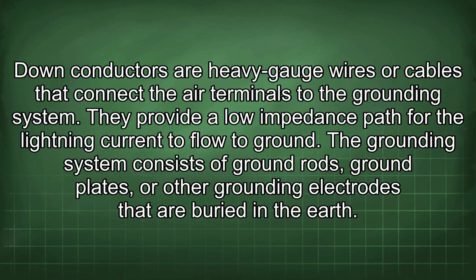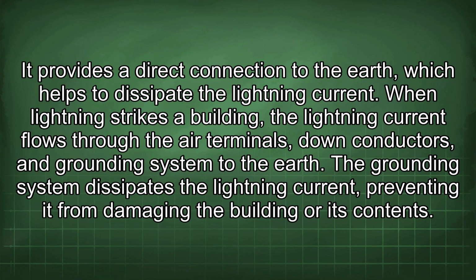Down conductors are heavy gauge wires or cables that connect the air terminals to the grounding system. They provide a low impedance path for the lightning current to flow to ground. The grounding system consists of ground rods, ground plates, or other grounding electrodes that are buried in the earth. It provides a direct connection to the earth, which helps to dissipate the lightning current.